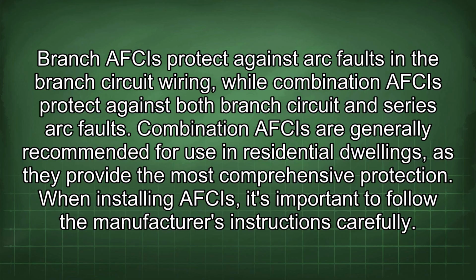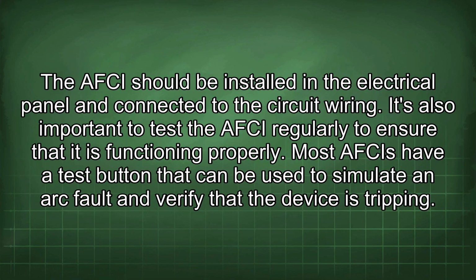Branch AFCIs protect against arc faults in the branch circuit wiring, while combination AFCIs protect against both branch circuit and series arc faults. Combination AFCIs are generally recommended for use in residential dwellings, as they provide the most comprehensive protection. When installing AFCIs, it's important to follow the manufacturer's instructions carefully. The AFCI should be installed in the electrical panel and connected to the circuit wiring.